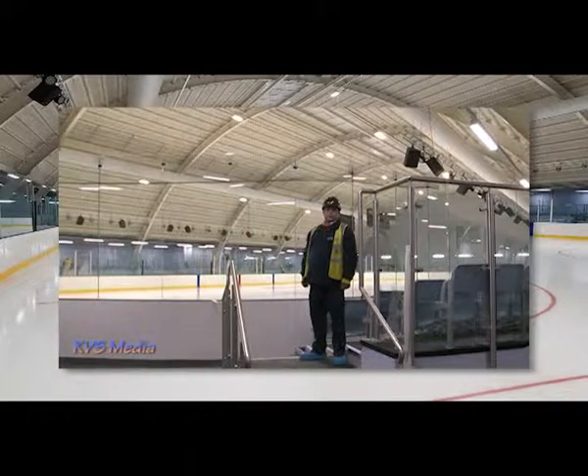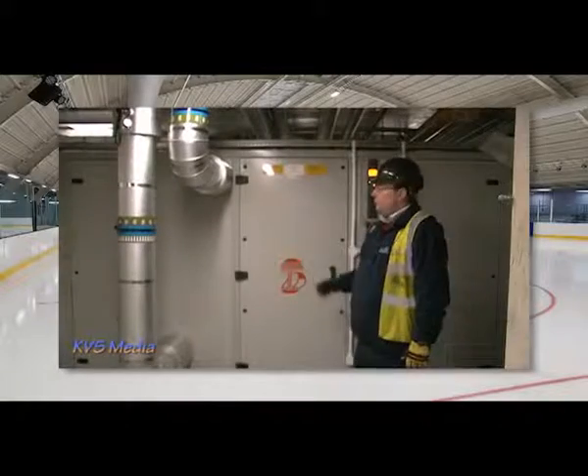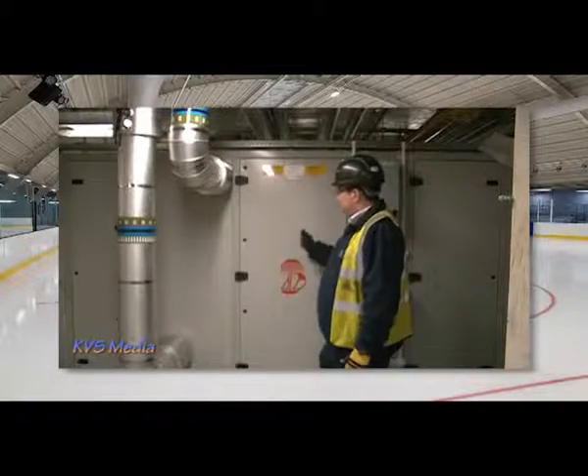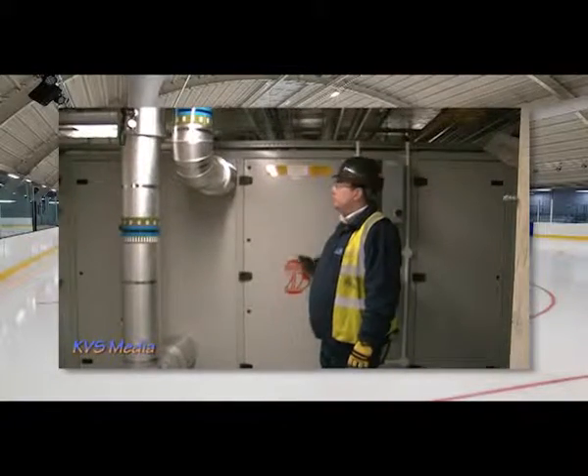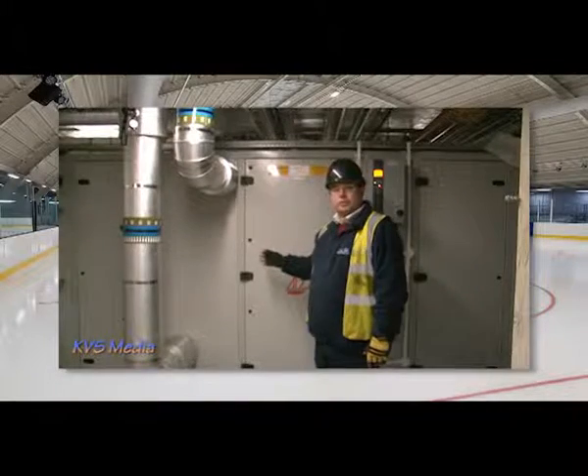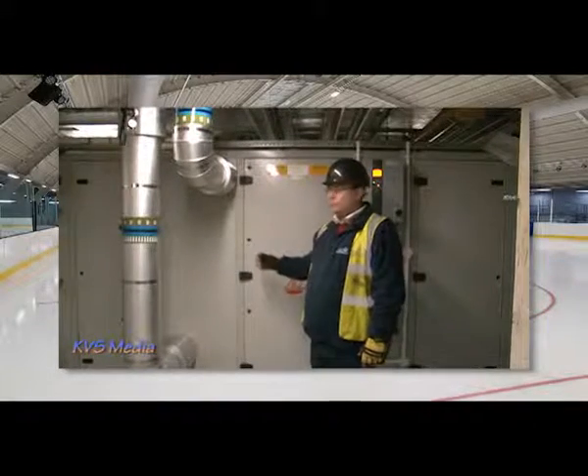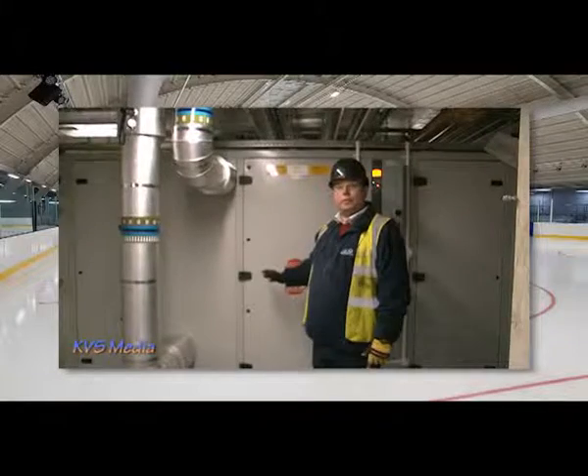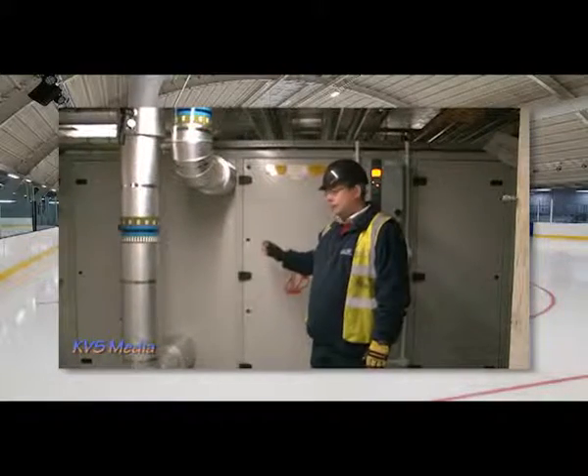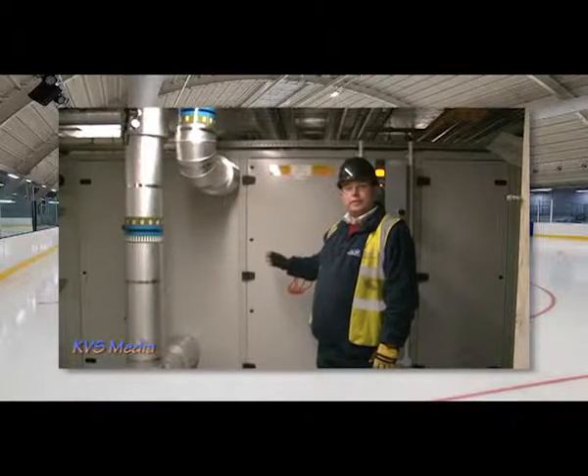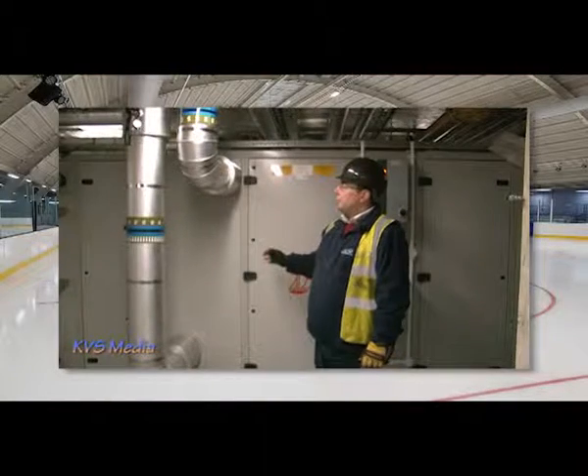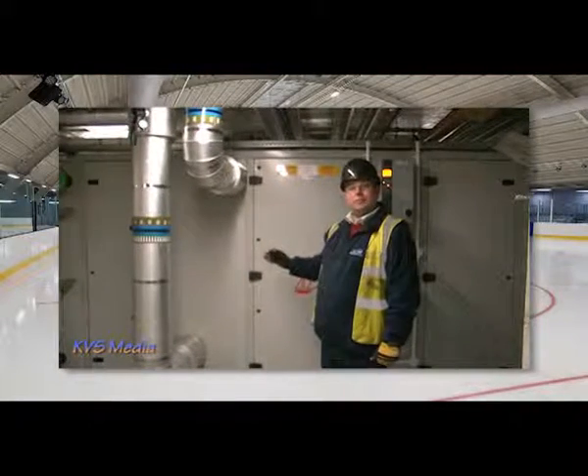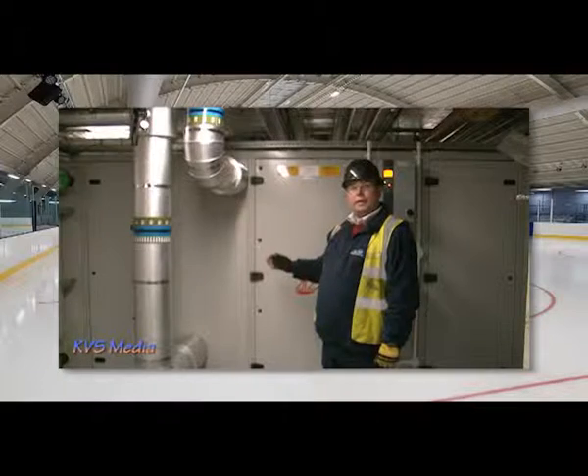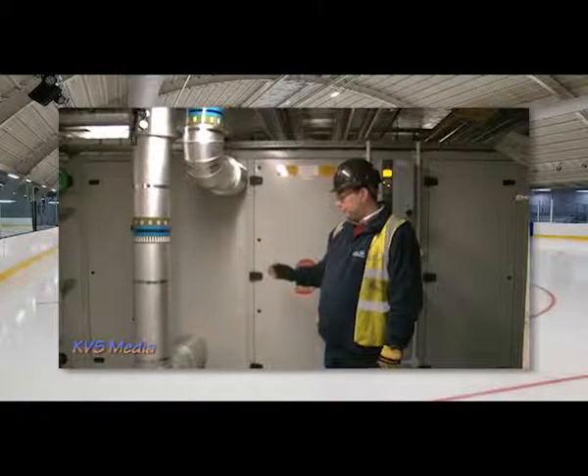Moving on, we now come past the entrance hatch for the motors, and we move on to the chilled glycol section, which houses a 300 kilowatt cooling coil for dehumidifying and condensing out any moisture into the air. This coil typically operates around a -1 inlet with a 3-degree outlet.